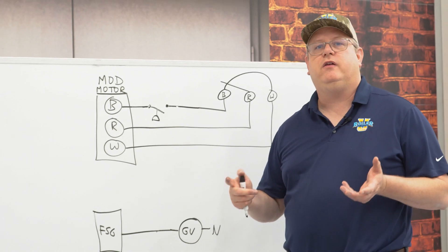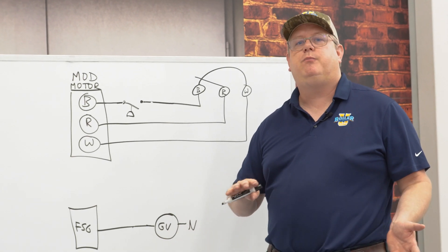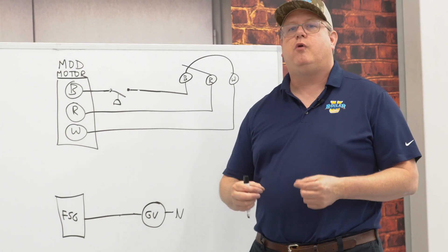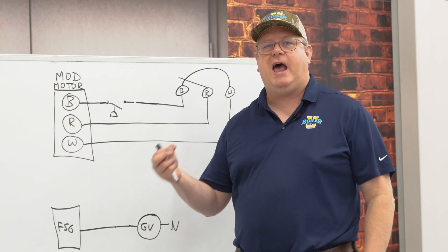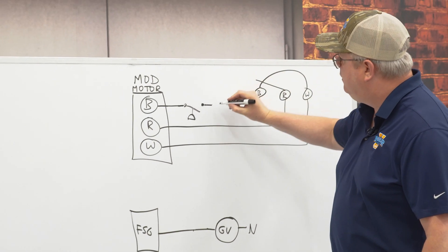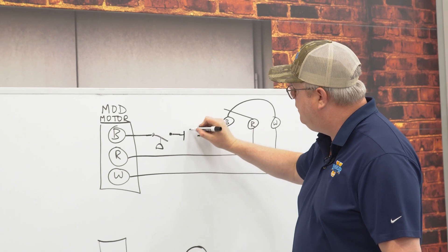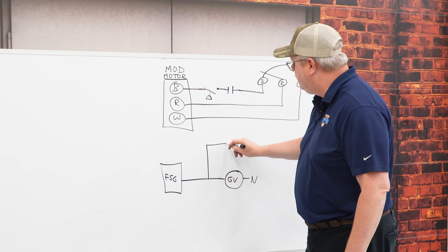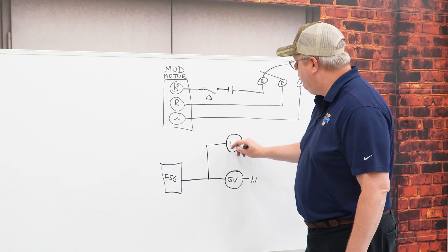Now, if I've got a boiler that cycles a lot and I want to prevent it from going to high fire or out of low fire for a duration, it's simple to add that to our firing rate limit circuit. Essentially, we just add an additional contact via relay and we can come off the flame safeguard control to the coil for that relay.